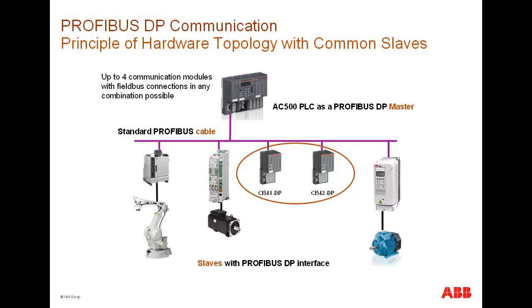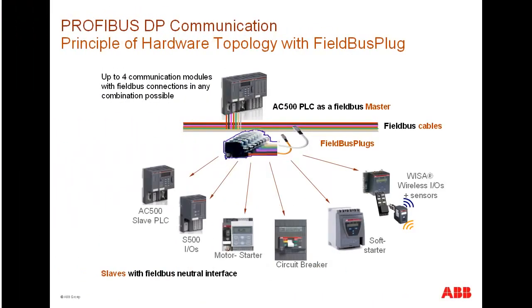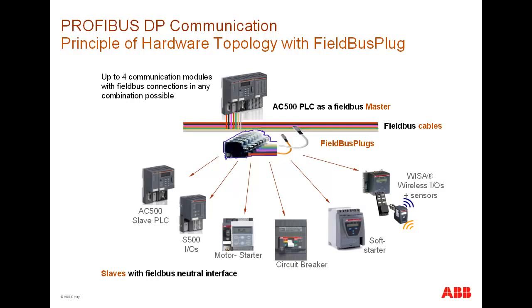One S500 bus module could accommodate up to 10 I/O modules in any order. Another connection possibility is the use of ABB PROFIBUS field bus plug between the DP master and the slave stations. This field bus plug enables us to connect field bus neutral slaves from ABB, like motor starters, circuit breakers, soft starters, wireless sensors, and so on via PROFIBUS DP. Additional field bus plugs are available to support other field bus protocols such as CANopen and DeviceNet.